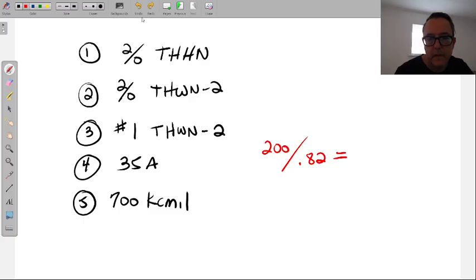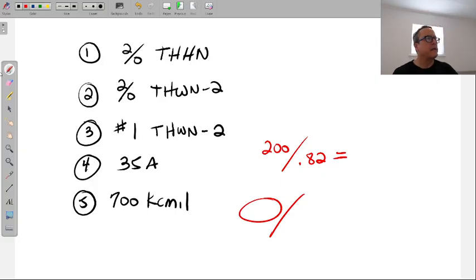Mr. Perez, when would we use table B? Which is table B? 3, 10, 15, table B, 1, 2. Sorry, the second one. That says it's ambient temperature correction factors based off of 40 degrees Celsius. Yeah, when do we use that one? That one's going to be for motors. Oh, okay. Yeah, that one's going to be when you deal with motors.